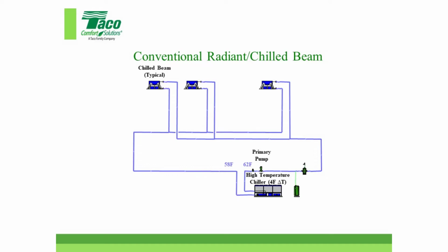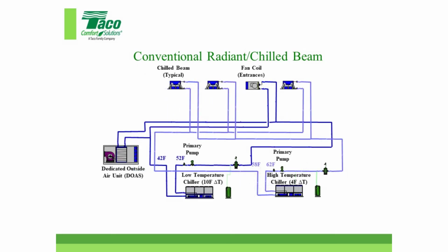Instead of taking care of the temperature in this room, in the mechanical room, we're going to do it at the zone. And there's other systems similar to this out there. We have a different type of approach. But notice, instead of at least 4 pipes, and this is just chilled water, right? I'm not even talking heating right now.